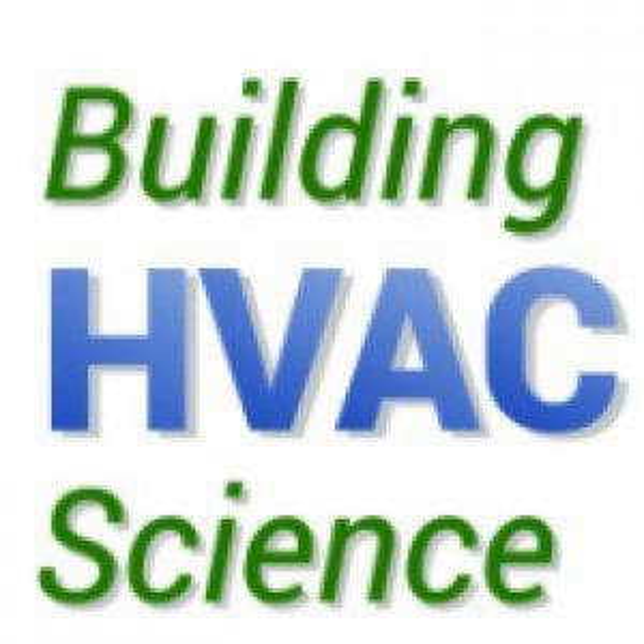Those machines work alternately, either as a fresh air appliance or as an air source heat pump. But the good news is every 30 minutes, you have the exact same amount of fresh air as a continuous ventilation equipment. This is permitted by ASHRAE 62.2, which states you've got 3 hours to bring in the exact same amount of fresh air in a non-continuous way compared to continuous ventilation. The good news is we are 6 times compliant with that request from ASHRAE 62.2. Not only that, we're doing every half hour a better job than any HRV ERV you can think of.